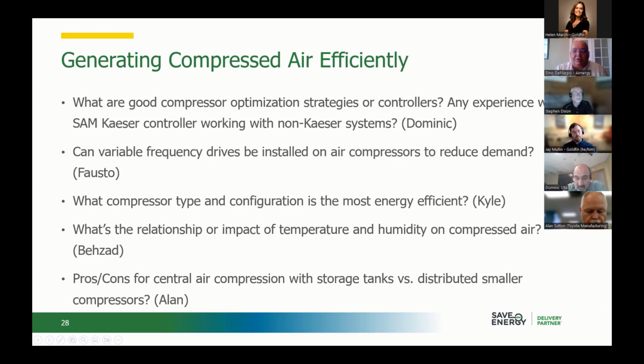Can variable frequency drives be installed? Yes, VFD drives can be installed on compressors, but there has to be a little bit of work done to analyze whether the compressor will work efficiently with the existing motor controls. So it isn't as simple as just throwing on a VFD drive onto a motor control and believing it's going to work properly.